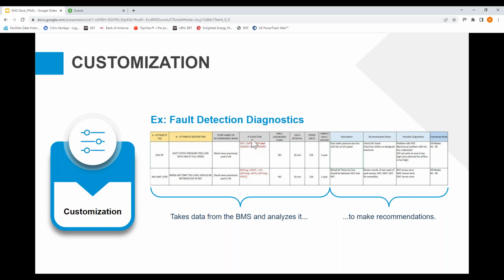So let me go ahead and walk through an example. I'm going to walk through one of the ones on the screen, the lower one where it says AHU MAT low. That is the air handler mixed air temperature sensor low. Don't worry about reading this chart, but ultimately you'll see some writing in red. That's the equation, and it'll go through that process and continuously be looking at those conditions.